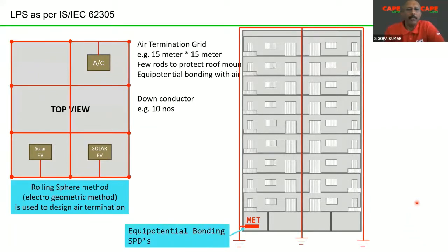The fourth subject, which is of equal importance, is equipotential bonding. What is equipotential bonding? You can see the down conductor is connected to the MET. MET is nothing but the main earth bus bar of the mains incoming panel. Down conductor must be connected to the protective earthing of the electrical system, and an equipotential bonding has to be made.